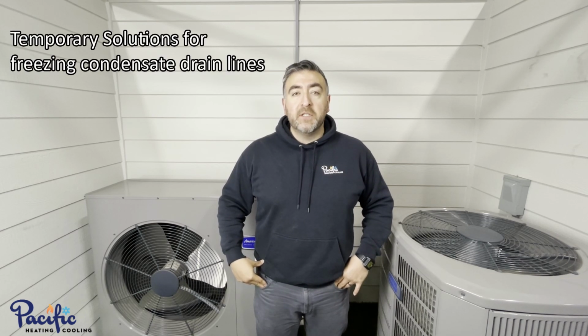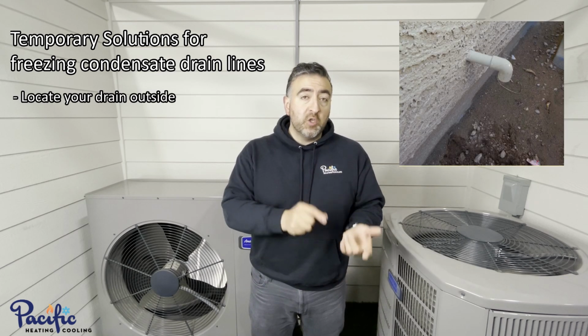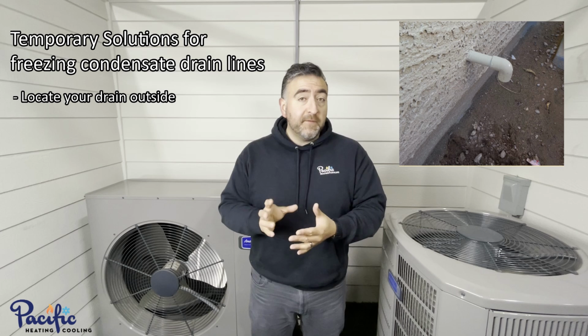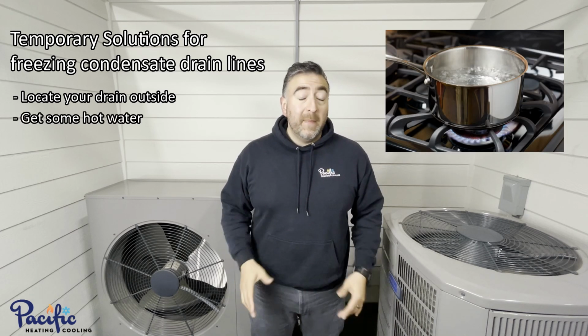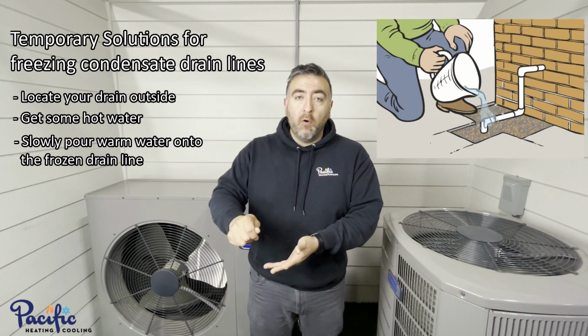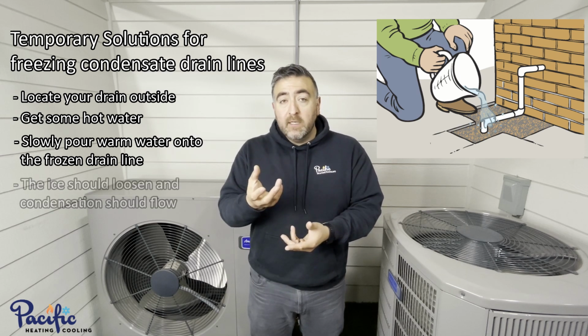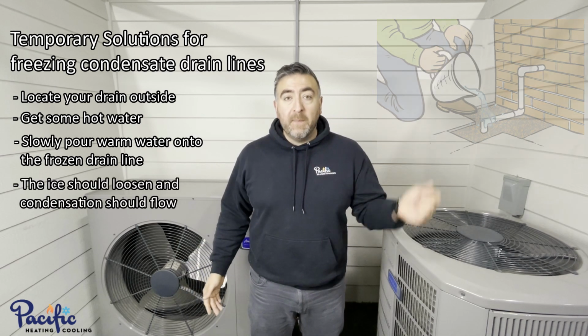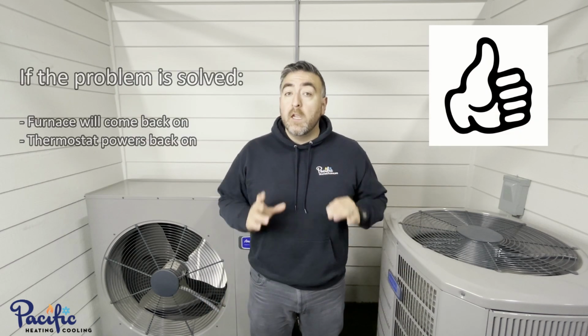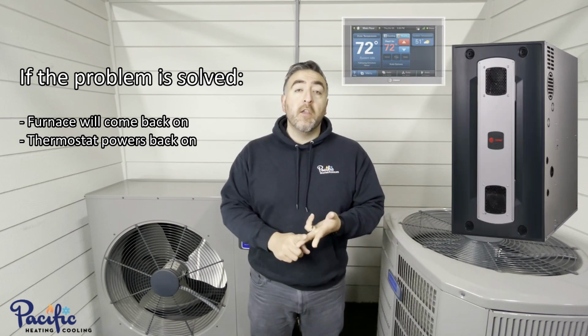If you've identified that you have a condensing gas furnace in your home and you're experiencing frozen drain lines, here are a couple temporary solutions that can help until the weather warms up. The first step you'll want to do is locating where the drain line comes from your home. If that's frozen up, get yourself some hot water. Make sure it's not boiling so you don't damage the PVC. Take your hot water and slowly pour it over the frozen portions of your drain line outside the home. Eventually, the ice should soften up, continue to flow, and your backup should be solved. You'll know this by your indoor unit coming back on, that means your gas furnace, and your thermostat powering back up.